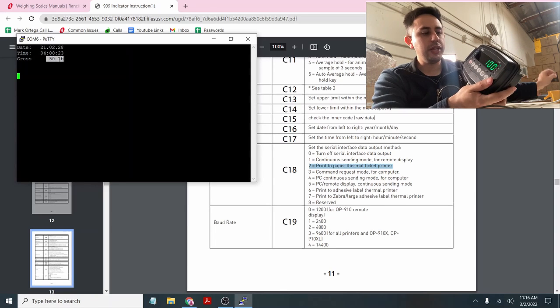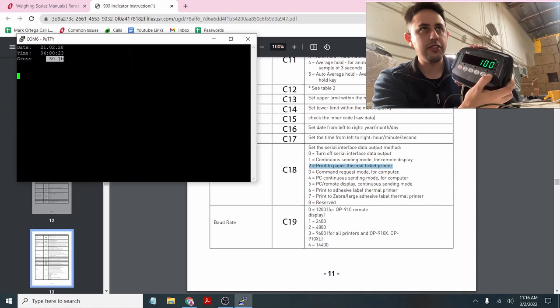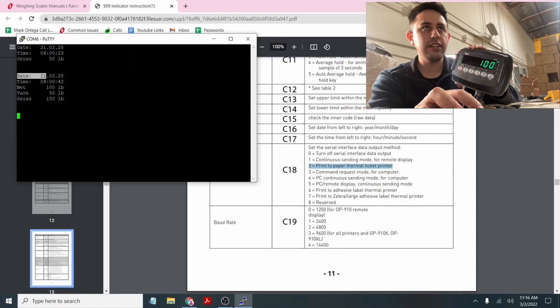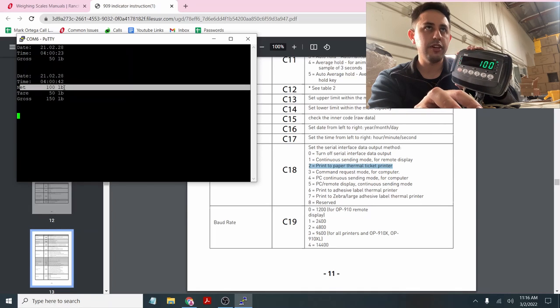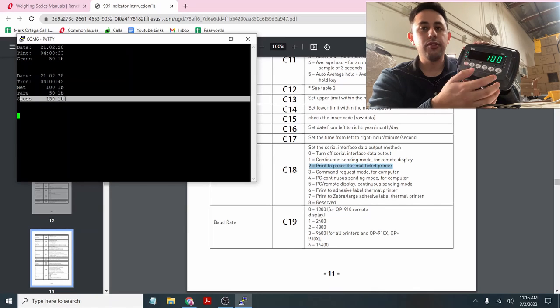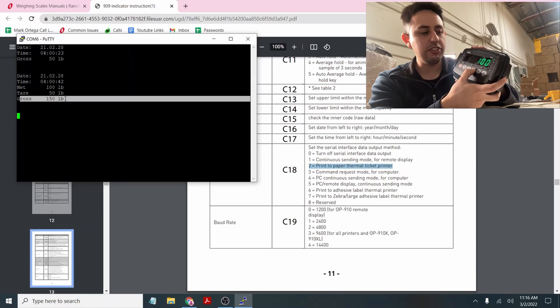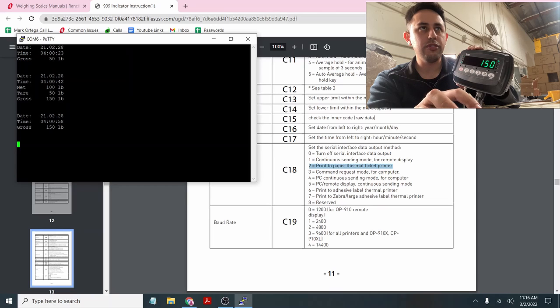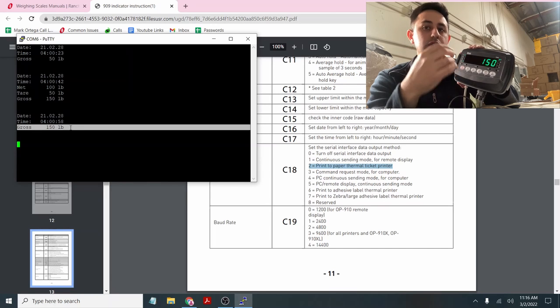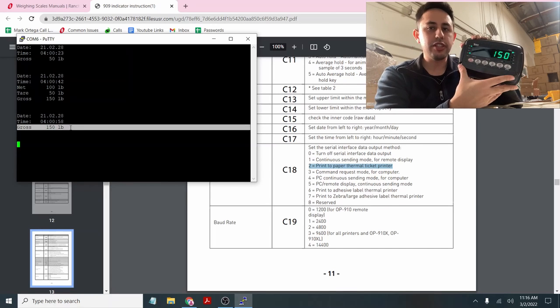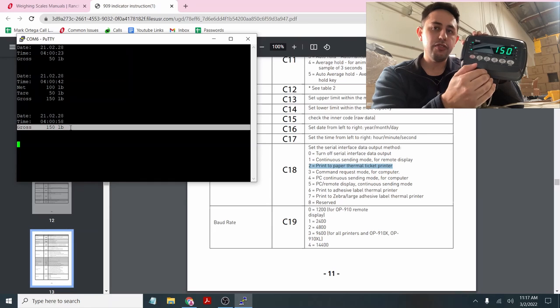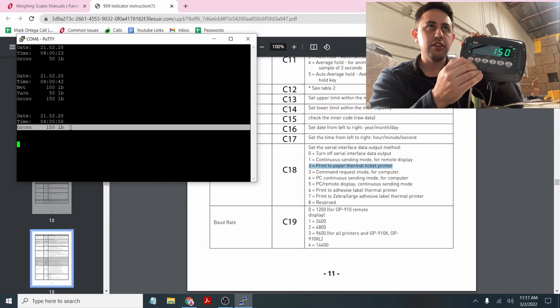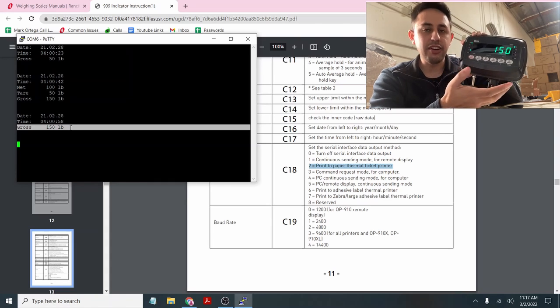And now I could add more weight, 100 pounds. And when I print, you'll see now it says date, time, net weight of 100 pounds. I tared off 50 pounds and the gross weight was 150. So that will only show up if you tare something. If you didn't tare something, for example, I untare it, back to 150, and now it only shows date, time, and gross. So just so you know, that's how the string output comes out from this device. If you don't see your net and tare, it's because you most likely didn't tare anything.